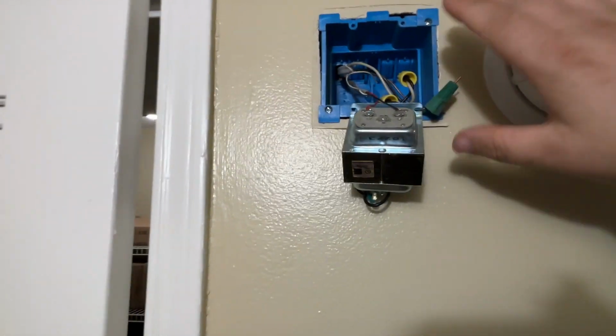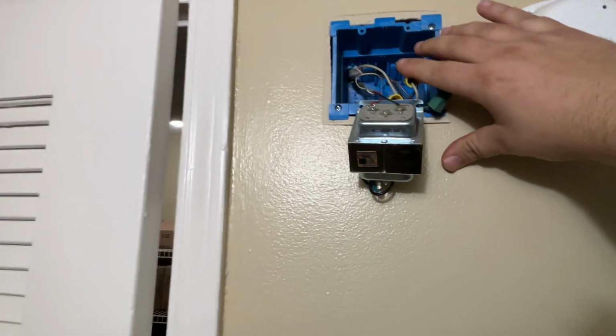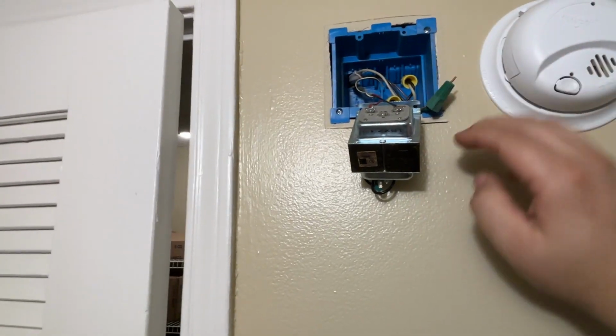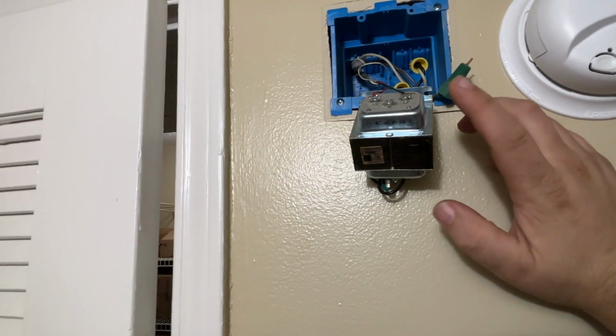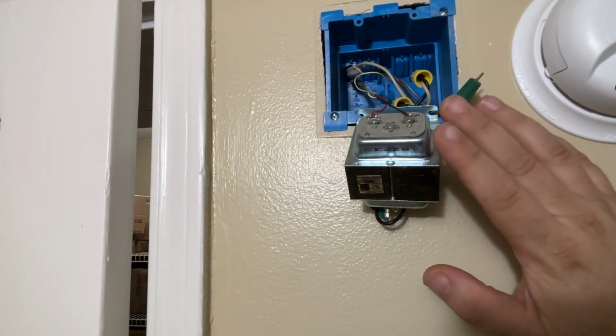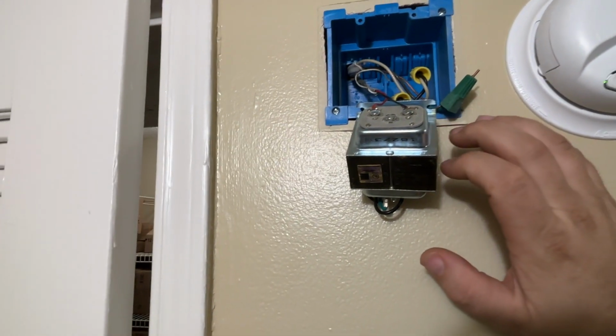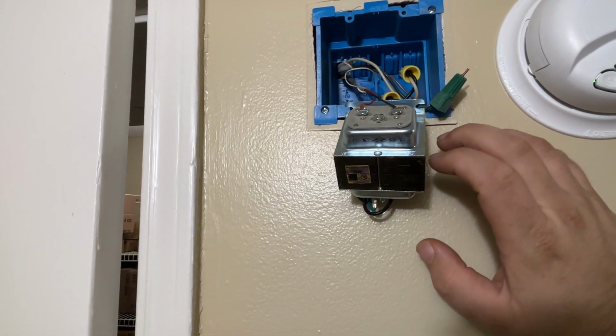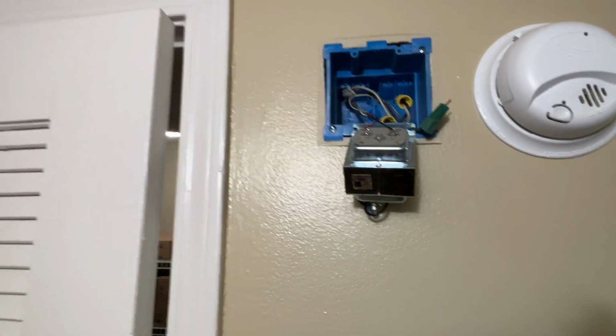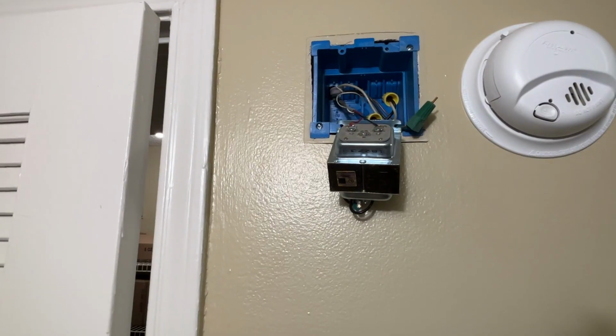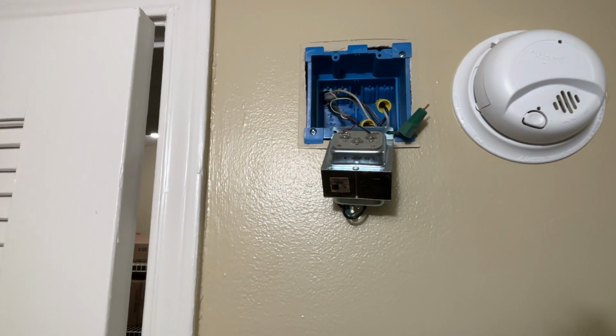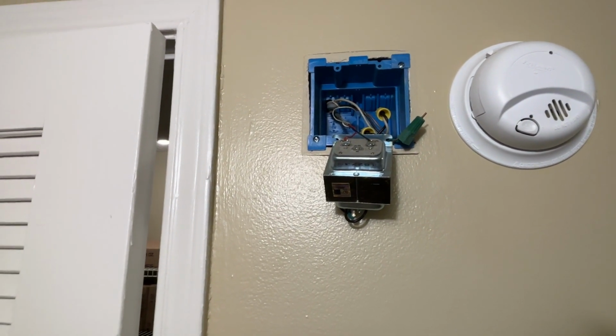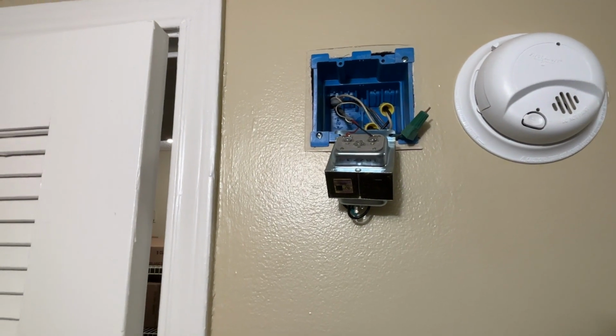Just a quick recap. If we have 120 main coming into our transformer and we have, in this case, close to 30 volts coming out, then our transformer is good. If we have power in and out through the transformer, and we have power to our switch but we don't have power out of our switch, then we know the switch is bad and needs to be replaced.